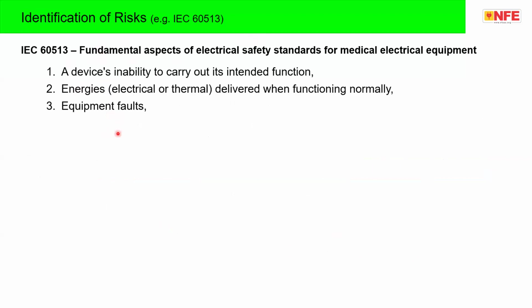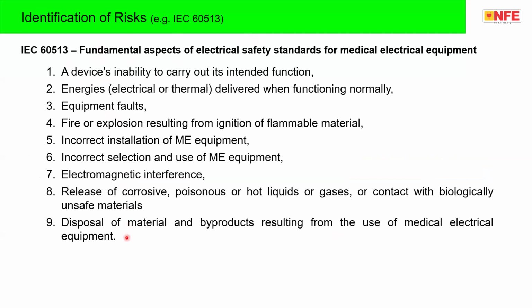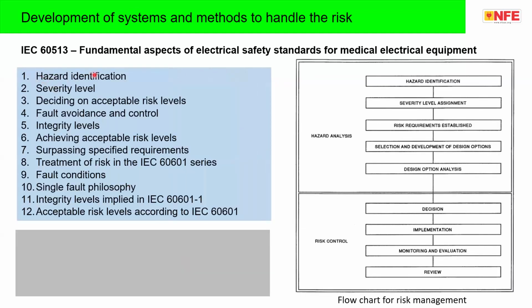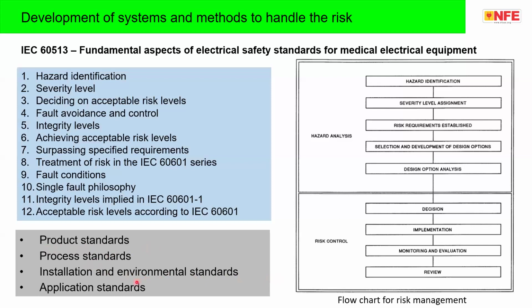IEC 60513 explains the different types of risk involved in a hospital or in a medical location, such as a device's inability to carry out its intended function, energies, equipment fault, and all the risks are identified in this particular standard. Now, hazard identification is number one. Then the severity level: what is the limit of a certain hazard? Decide on acceptable risk level, fault avoidance and control, integrity levels. Basically, the risks are converted into engineering practices. And these engineering practices are again developed into product standard, process standard, installation and environmental standard, and application standard.